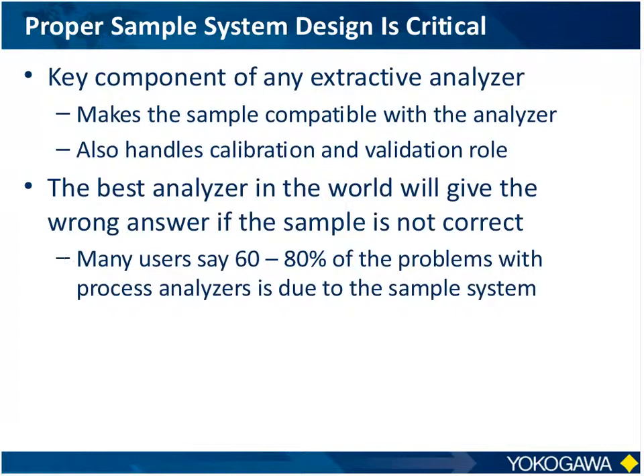But it all needs to be done properly because over these last 30 years when I've talked to customers and clients, I ask them, what headaches do they have with their equipment, and it's almost never the analyzer itself. 60 to 80% of their problems are with the sample system. Either their filters are not the right type or they're getting contamination between the different sample lines and it's causing strange readings.